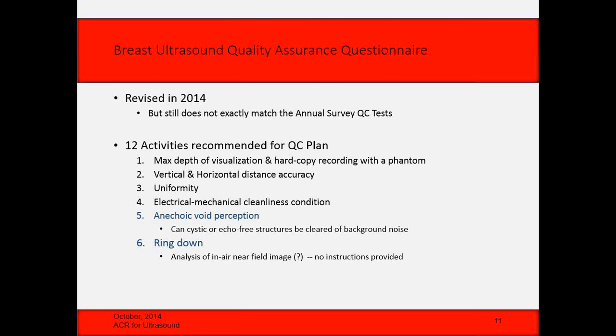So sometimes you can see what looks like dropouts, and you do some further tests and you confirm that there really is some problem, but you can also see what looks like defects, and then you test everything and everything's okay. So the ring down is a function of several different things: the timing of the TR switches, the way that the information is interpolated when it's received, and the quality of the transducer. If somebody put too thick of a membrane on it, you'll have too much ring down. You'll also attenuate the ultrasound more than it should be.